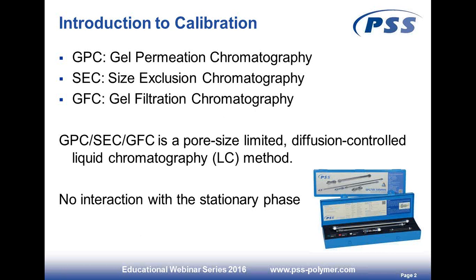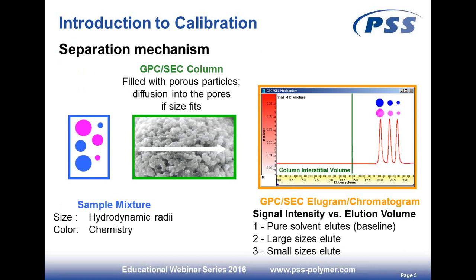GPC-SEC/GFC is a pore-size-limited, diffusion-controlled liquid chromatography method. In contrast to HPLC, we don't want any interaction with the stationary phase — we want to separate polymers according to the accessible pore volume in the column. The column is filled with porous particles, and inside the particles there are pores of different sizes; polymers can only enter pores if their size fits.